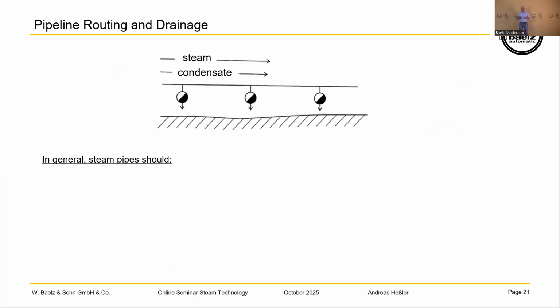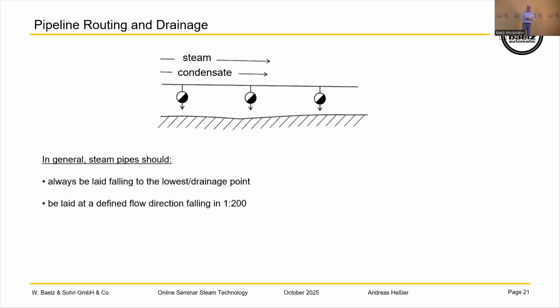Here are some slides. The next 3 slides are just for your information: how to install steam traps and what you have to check. Always install with a fall. When you have a fall, the steam trap has to be at the lowest point, of course. The water will go to the lowest point. And the fall should be 1 to 200.